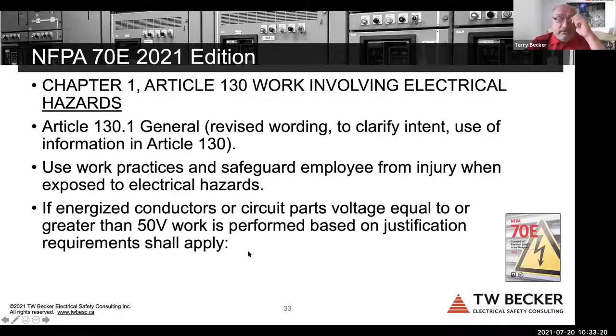One other thing I haven't mentioned, the other divergence here too, is Z462, the low end thresholds of application. 70E is still a 50 volt standard based on OSHA historically, but we technically deviate in Z462 in that we have 30 volts AC, and now we added and upped the voltage to 60 volts DC as the low end thresholds, where the standard really doesn't apply and you don't need a permit. So there's a technical deviation, 50 volts threshold in 70E, 30 volts AC or 60 volts DC in Z462. All right, so back to Article 130.